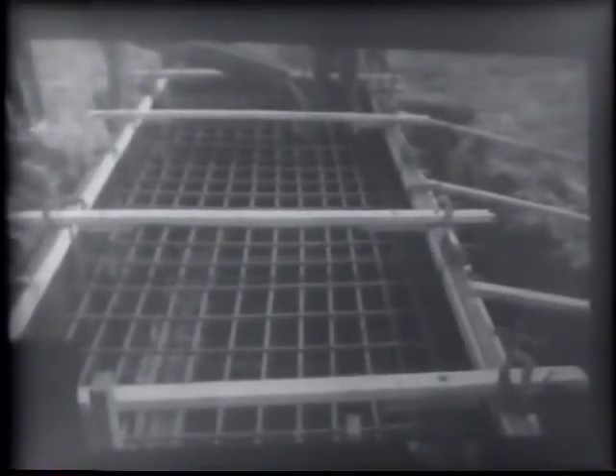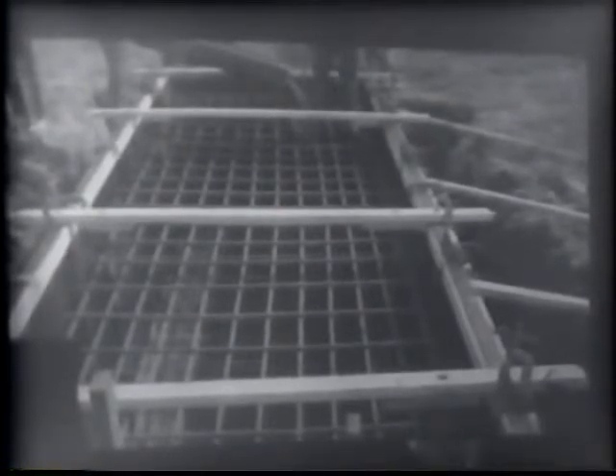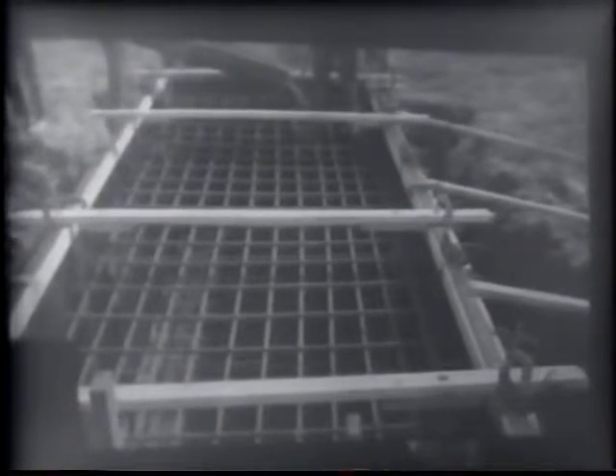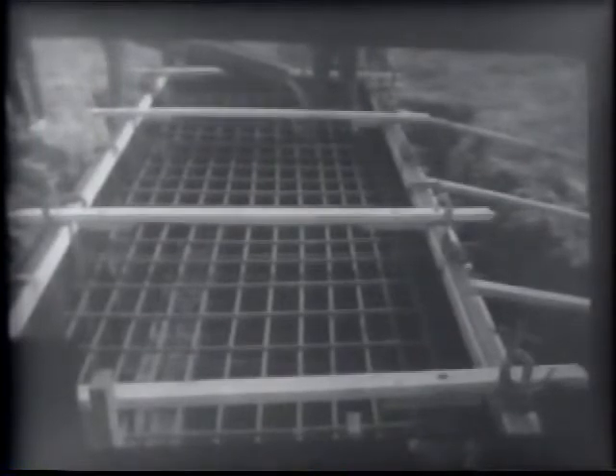This particular view here shows that we have to have a pretty heavily reinforced foundation for the different forces that exist in a circuit breaker. As I recall, a 161 kV circuit breaker, 10,000 MVA, is in the order of, what figures have we been using, Tom? 140,000 pounds? Or is that the total, including the uplift? 40,000 pounds. Is it 40,000? 60, yeah, I think 63,000. 63,000 pounds. That would be the weight of a 161 kV 3-tank circuit breaker.